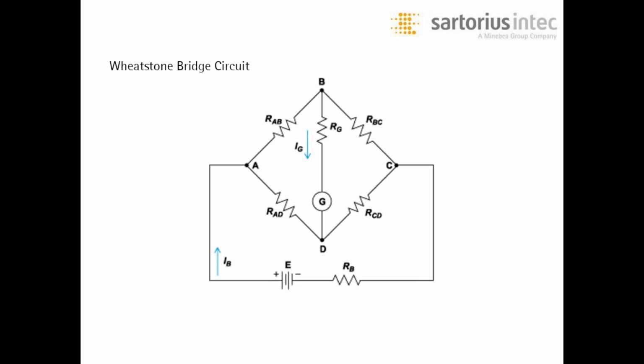When the metallic member to which the strain gauges are attached is stressed by the application of a force, the resulting strain leads to a change in resistance in one or more of the resistors. This change in resistance results in a change in output voltage. This very small change in output voltage, usually about 20 millivolts total in response to full load, can be measured and digitized after careful amplification of the small millivolt signal to a higher amplitude of 0 to 5 or 0 to 10 volt signal. These load cells have been used for many decades now and can provide very accurate readings, but require many tedious steps during the manufacturing process.